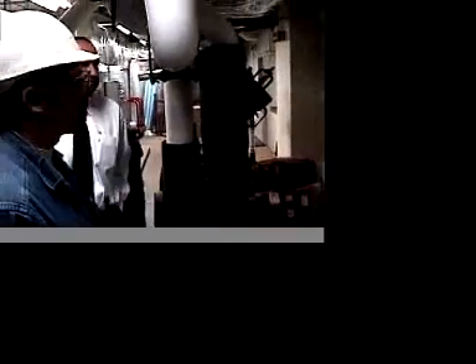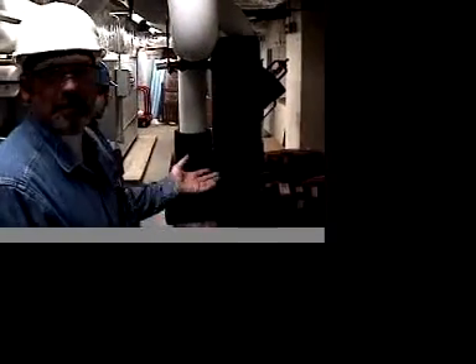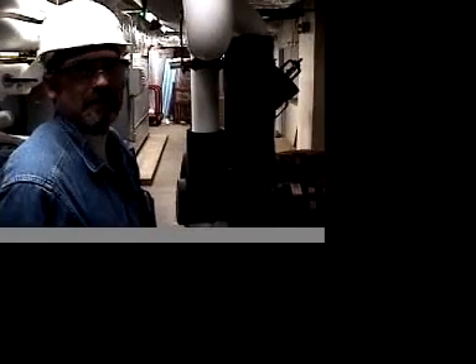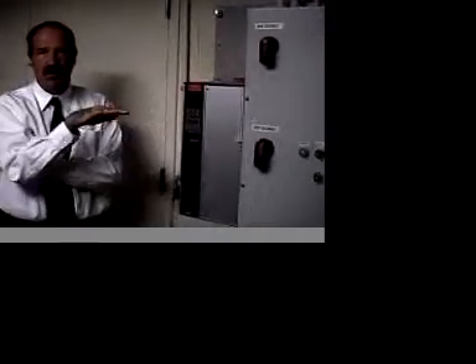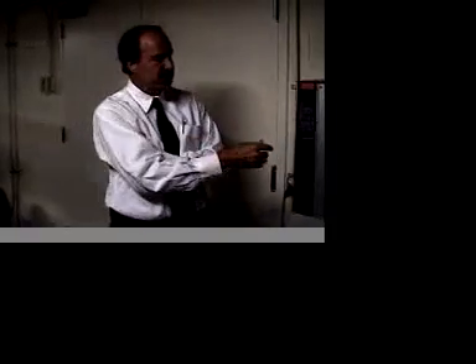So tell me about these pumps. These are redundant pumps? You only run one at a time. It's just like a backup if you need the other one. Okay, and then they are variable speed or variable frequency, whatever you call them? Right, with the drive, you set the point on here off of the end of the line static pressure sensor. That senses the line, it comes into here, and then it maintains a level. It's maintaining a level so that all units can always get pumped. As more units turn on, the pressure will start to decrease, and then the pump will increase, and it'll go up and down to maintain this.